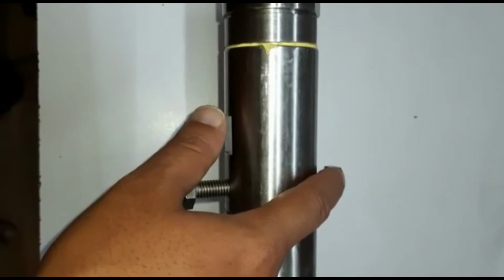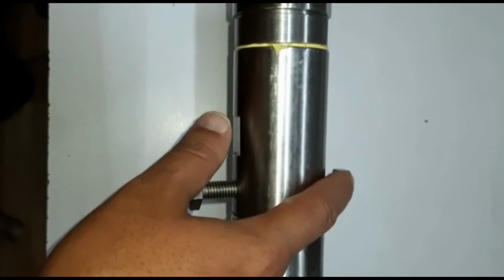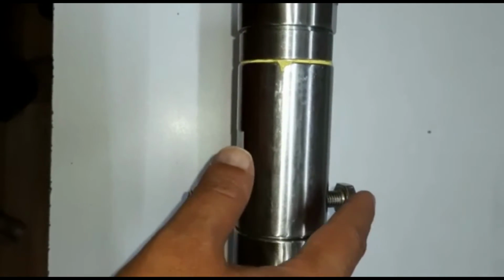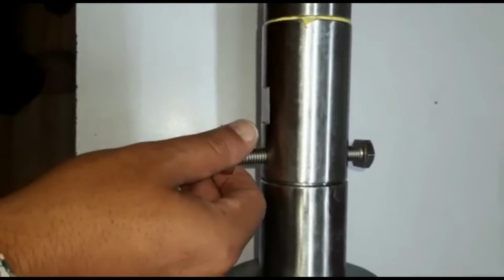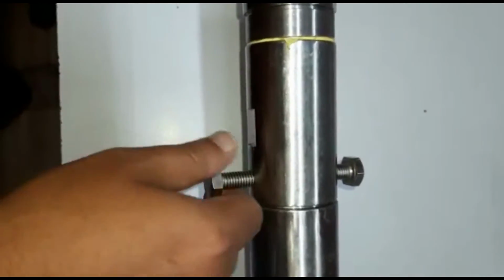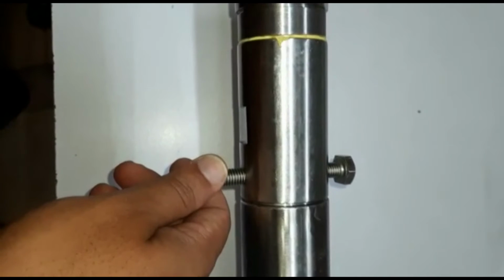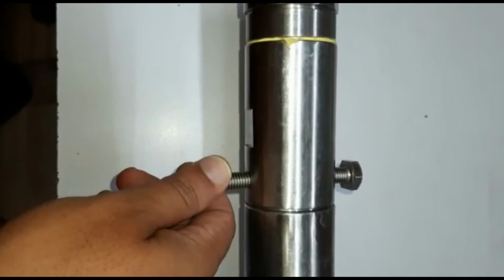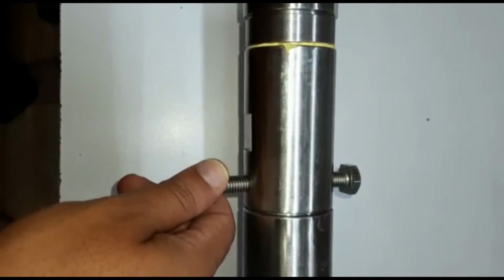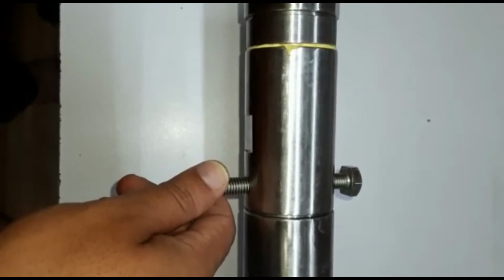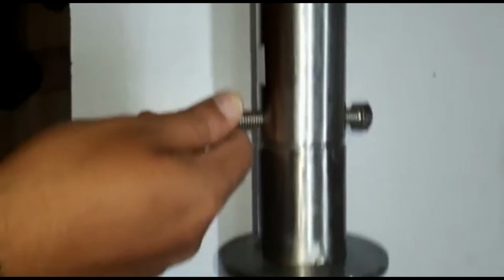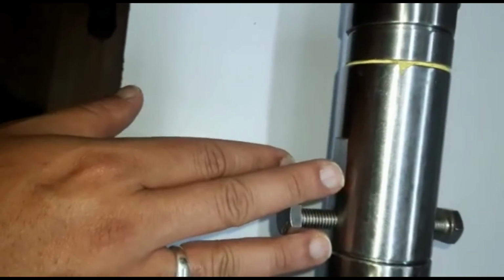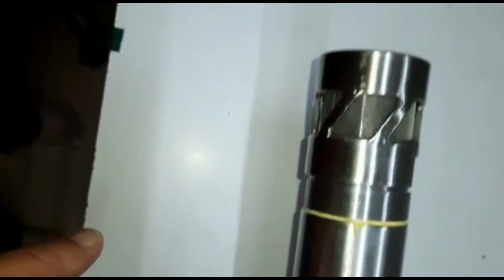And the other precaution is that of these two bolts, one has the thermocouple and the other one is for a test thermocouple for calibration. So it is essentially empty. But please do not rotate this because that can mess up the thermocouple inside. For uninstalling the thermocouple or the oxygen sensor, first they have to be disconnected from inside this, and only then can it be dismantled. So these are the precautions that one needs to keep in mind.